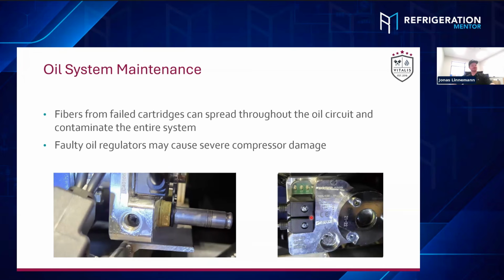Yeah, you really don't want to have the oil traveling out into the system, because as soon as that's happening, no matter what, it's more difficult to get that back into the oil reservoir and into the compressor. Yep. But that was a good point you made. This oil regulator type actually came with an inbuilt strainer. I didn't add that picture to this slide, but the amount of contamination and the amount of fibers was just that heavy. And we deal with big differential pressures in CO₂. The strainer couldn't catch that big amount of fibers, and the high DP then just cracked the strainer. And then the fibers were traveling into the valve seat itself. So the first goal is always to avoid the contamination happening, right?